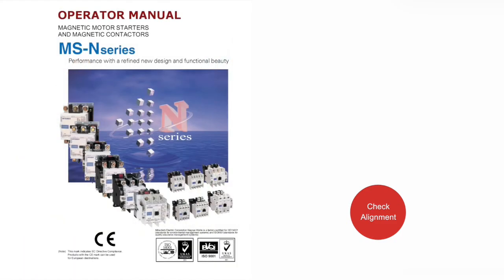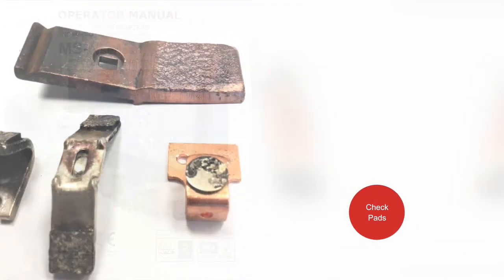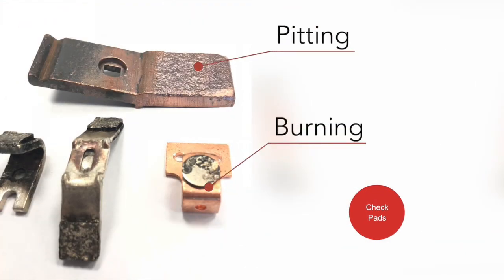Next, check the pads for pitting or other wear that could cause electrical arcing. Shown here are a few examples of pitted and burned contacts. Arcing can cause the movable and stationary contacts to weld together, creating a dangerous condition.